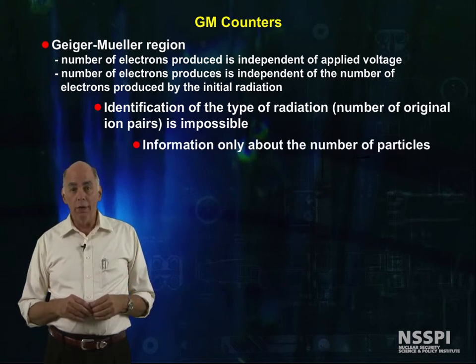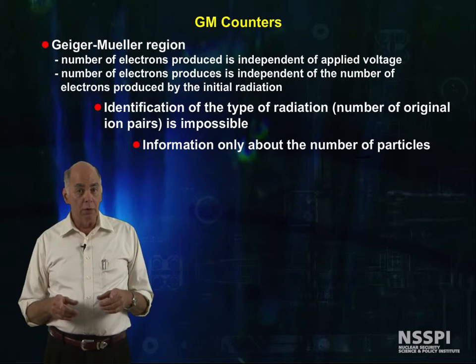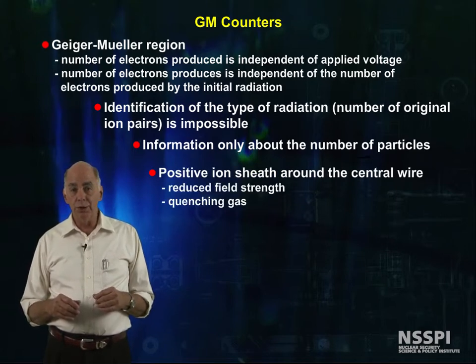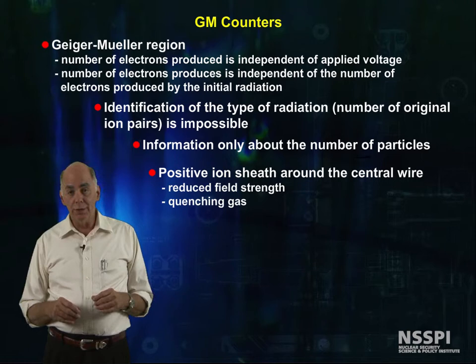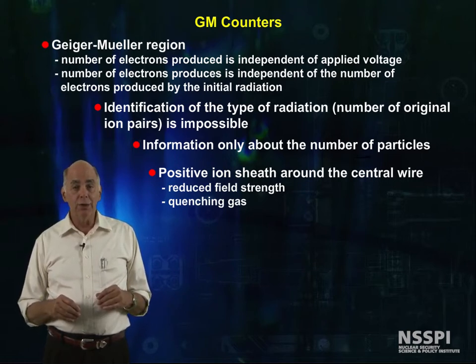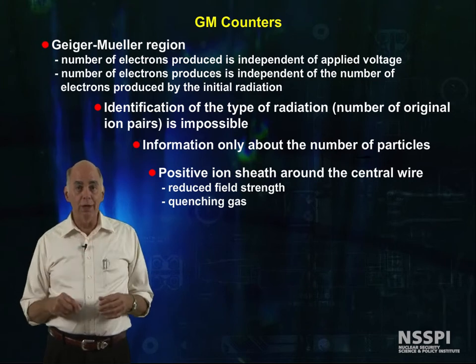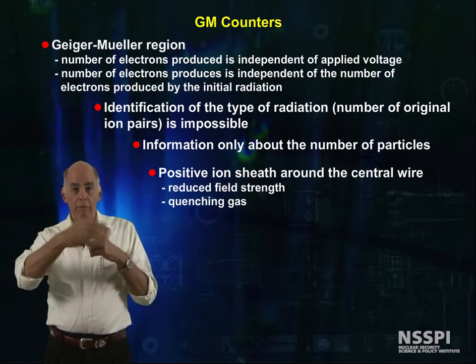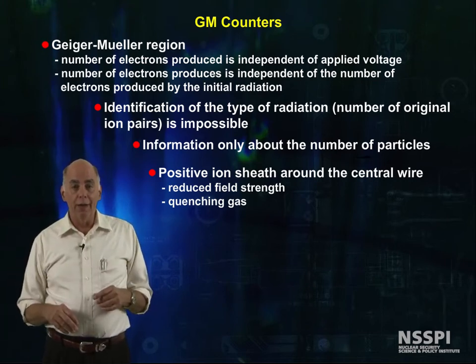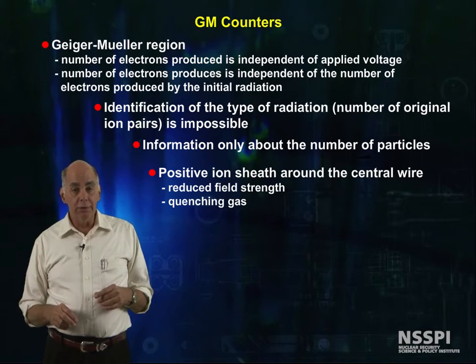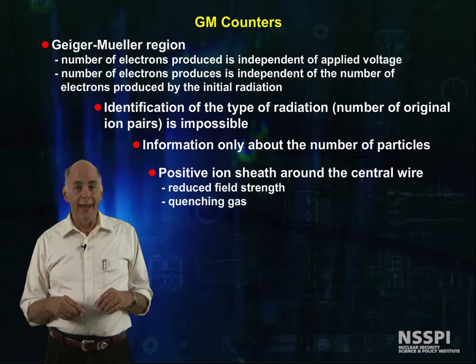The only information available is about the number of particles. The GM detector would discharge continuously after the first pulse, except that positive ions around the central anode wire form a sheath around the wire, reducing the apparent field strength. Also, a quench gas is normally added.